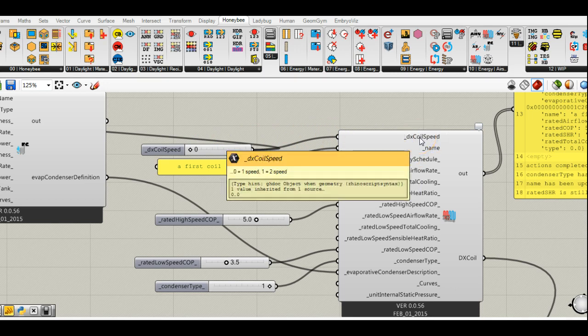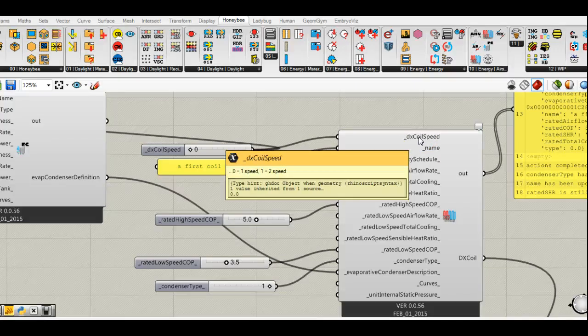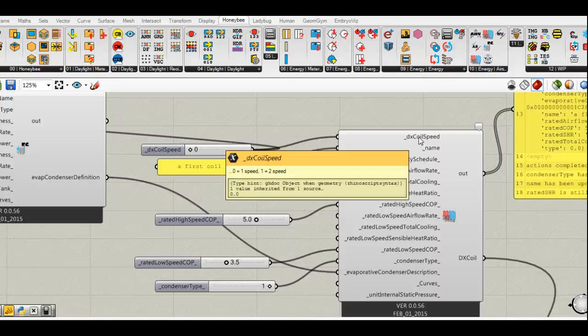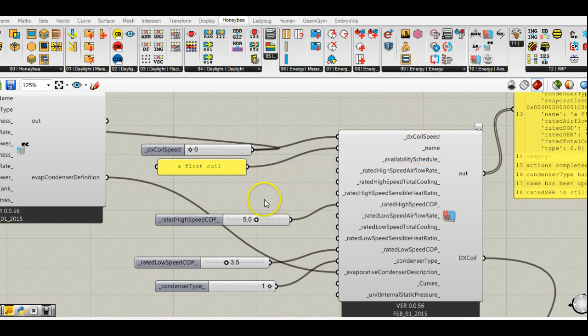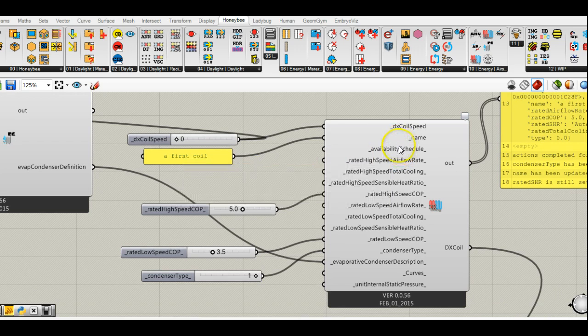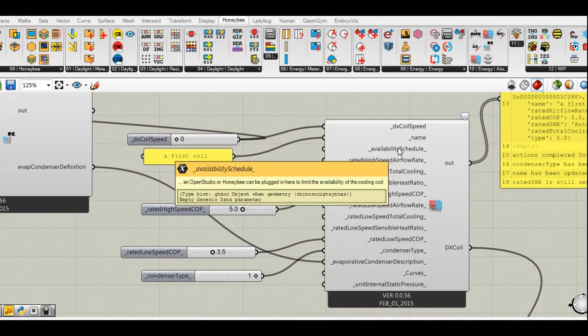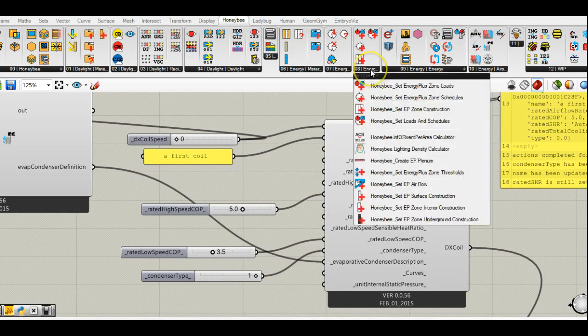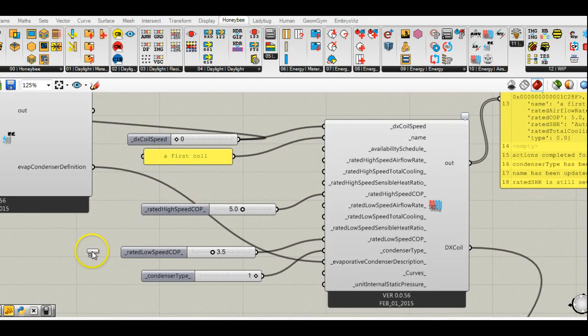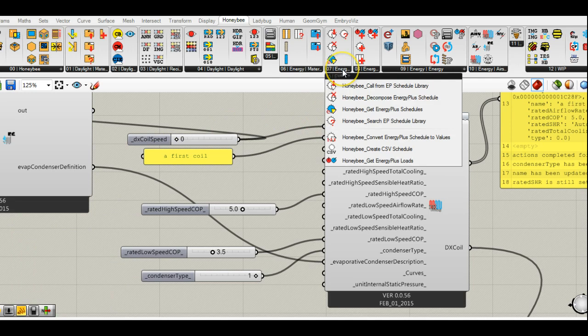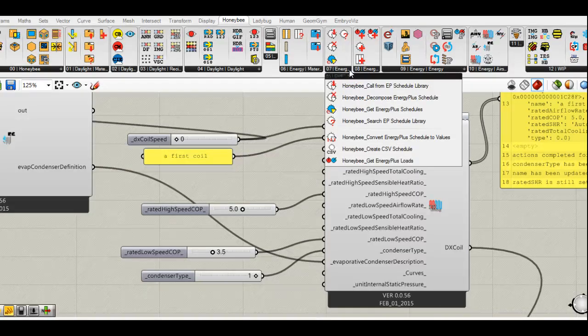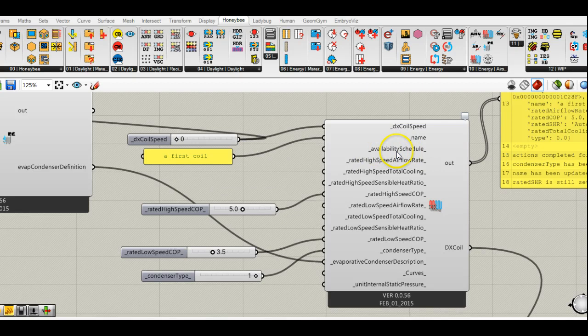Zero is one speed. One is two speed. EnergyPlus actually offers more speed control than this. But OpenStudio doesn't currently support more than two speeds, but that's a pretty good start. You also have to provide a unique name for it. The availability schedule, you only have to provide a name of a schedule here. And this has to be a name that's already available in Honeybee. So if you want to find all the schedules, you probably want to use a component like this. And you can search all the schedules and find one that works for you. I could probably give another tutorial on that if you're not familiar with that, or you can always reach out to me with questions. But it has to be a valid name, basically, or else an error will be thrown and it won't be used.